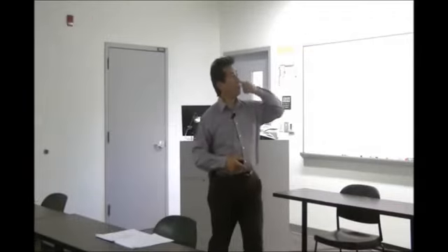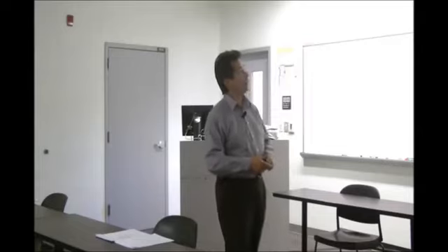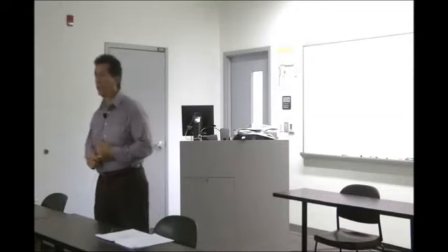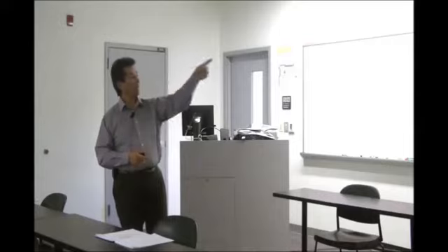So again, condition assessments define the needs. Now we determine the condition of the equipment. What's the working order of the equipment? Getting back to that reliability and performance component: how well does that one operate, and how reliable is that piece of equipment? Verify maintenance frequencies, determine if the maintenance quality is appropriate, and then validate the tasks associated with the piece of equipment. And note and rate identified deficiencies by criticality. So how critical would those be?